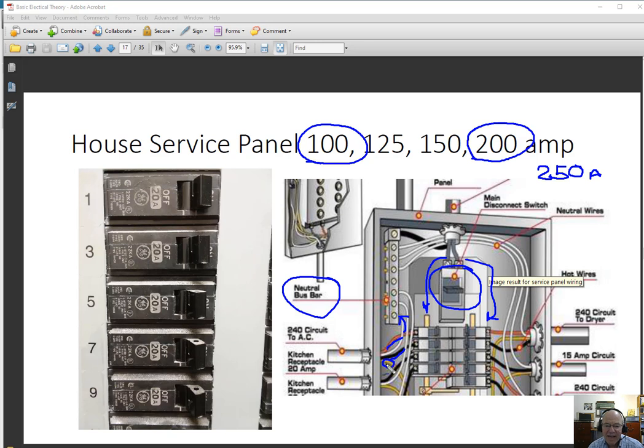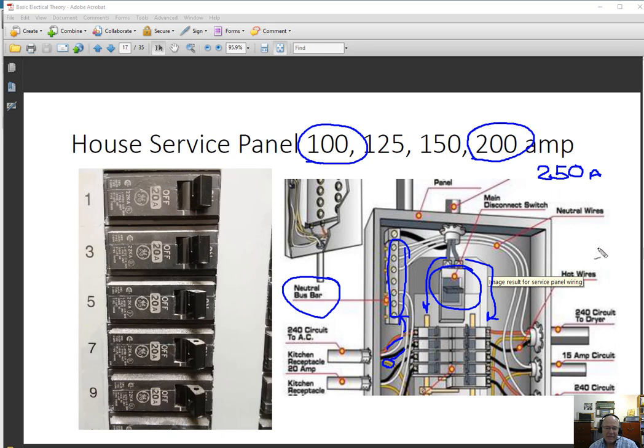Since all the neutrals are connected together — they're all screwed down onto the neutral bus bar — you can't connect the hot wires together. Also on that neutral bus bar is a bare wire. If you look at the cables coming out of your service panel, they're going to have hot wires, a neutral wire, and a ground wire. The neutral and the ground are all connected electrically together, and all of them return current back to the literal ground via a ground rod driven into the ground outside your home. Sometimes it's also connected to the plumbing system, so you can have a complete circuit where current comes in, goes through a device, and returns to ground.